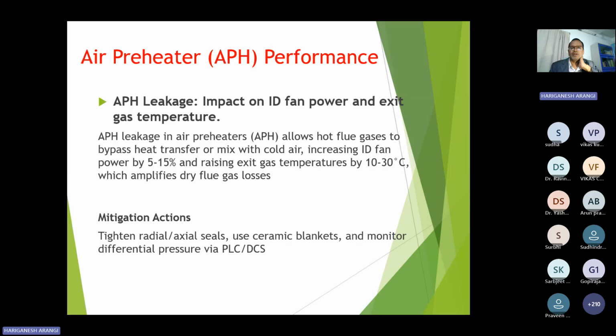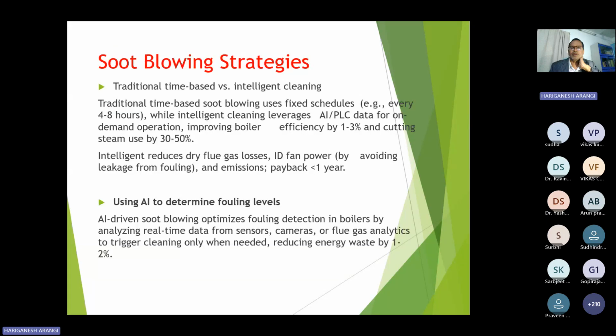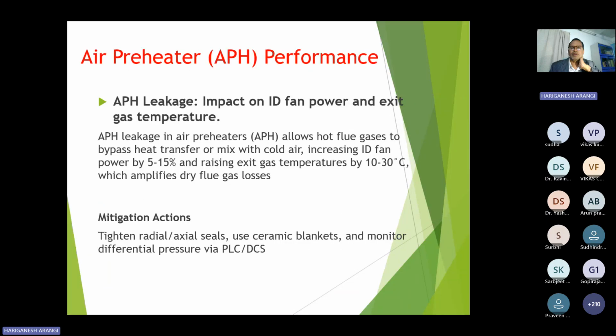And these losses we can observe in our DCS system or PLC connected system, where we can see, okay, on that computer, what we have shown, the DCS system, there we can observe different readings. When the air temperature at this air preheater is low, obviously it will affect the fuel heating area. The temperature will show that improper hot air is coming.